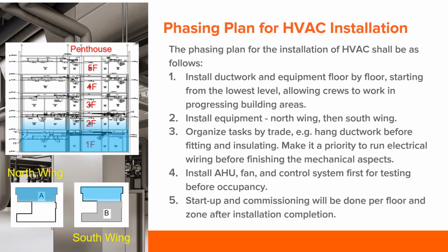Next, the north wing will have its equipment installed, followed by the south wing. The tasks will be organized according to the trade, starting with the installation of ductwork, followed by fitting and insulating. It's important to run electrical wiring before mechanical work is finished. The air handling unit, fan and controls will be installed first to allow for testing before occupancy. Startup and commissioning will occur per floor and zone after each area's installation is complete, from the first to fifth floors and finally the penthouse.